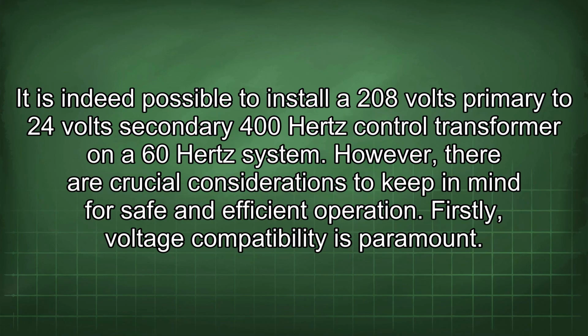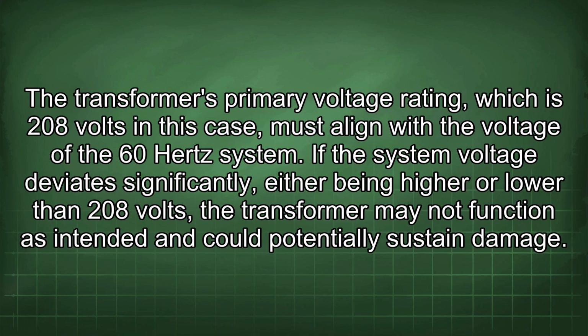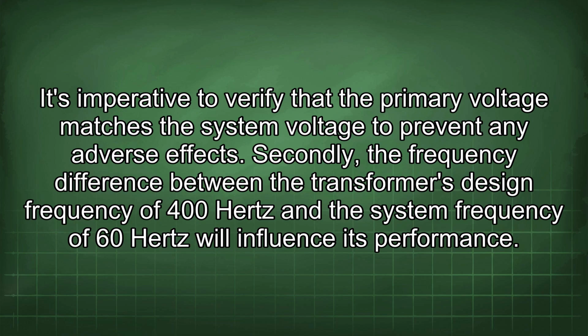It is indeed possible to install a 208 volts primary to 24 volt secondary 400 Hz control transformer on a 60 Hz system. However, there are crucial considerations to keep in mind for safe and efficient operation. Firstly, voltage compatibility is paramount. The transformer's primary voltage rating, which is 208 volts in this case, must align with the voltage of the 60 Hz system. If the system voltage deviates significantly, either being higher or lower than 208 volts, the transformer may not function as intended and could potentially sustain damage. It's imperative to verify that the primary voltage matches the system voltage to prevent any adverse effects.